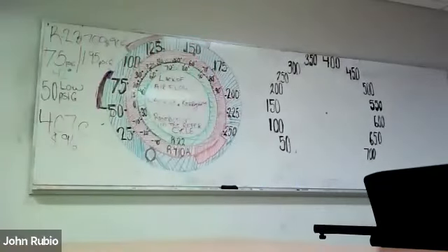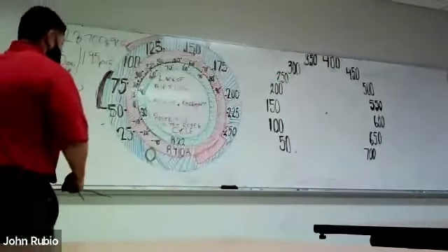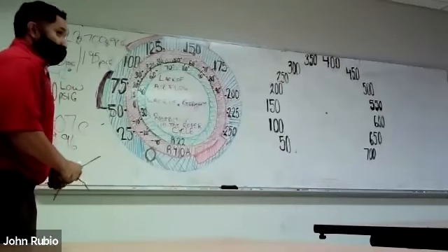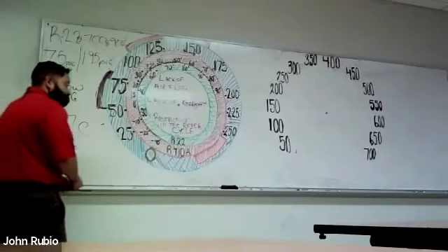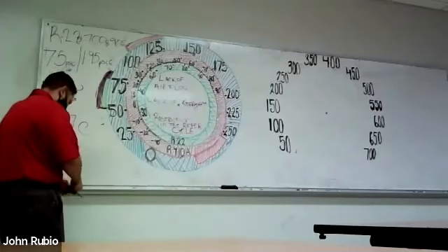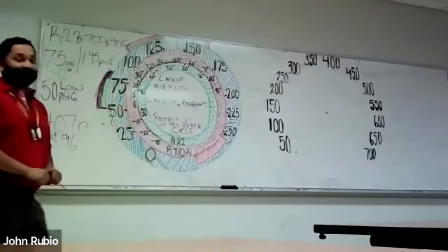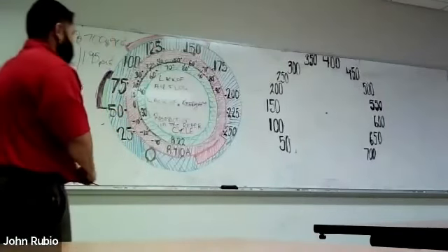We want to check subcool. We also need to use our high side if we want to see if we truly have a system that's low on refrigerant. Because if we truly have a system that's low on refrigerant, our high side will confirm that, or our high side will tell us, you're wrong. It's not low. The refrigerant you're missing, I have it, because there's a restriction in my refrigeration cycle. Only with your high side attached can you catch that.